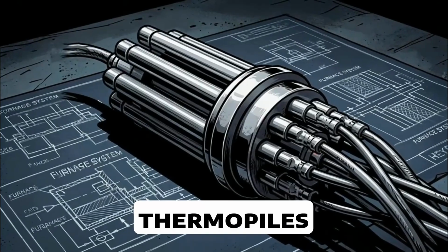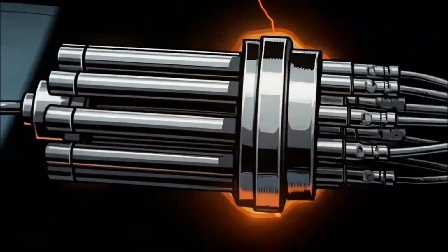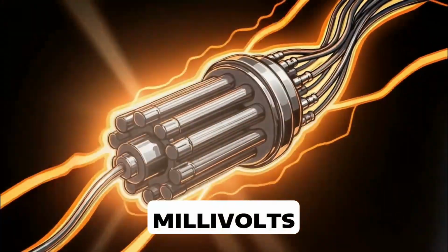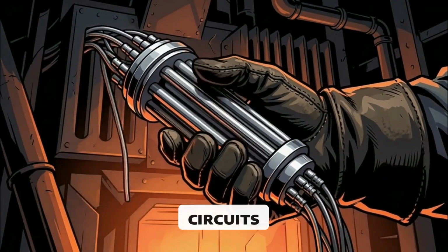Now, thermopiles. A thermopile is multiple thermocouples connected together. It produces more power, often around 250 millivolts to 1000 millivolts depending on design. Enough for millivolt systems and some control circuits.